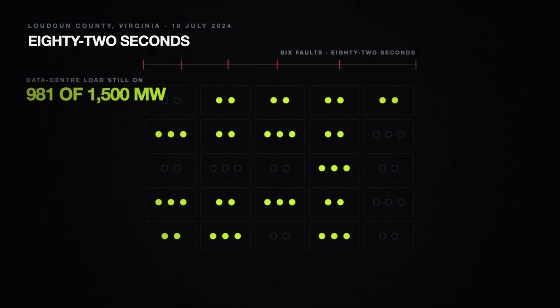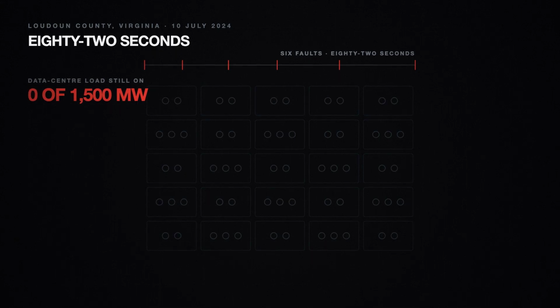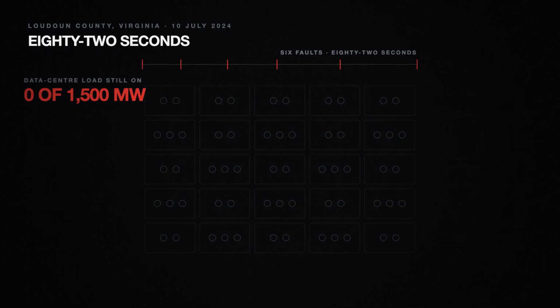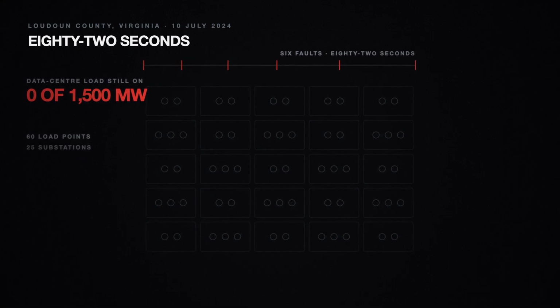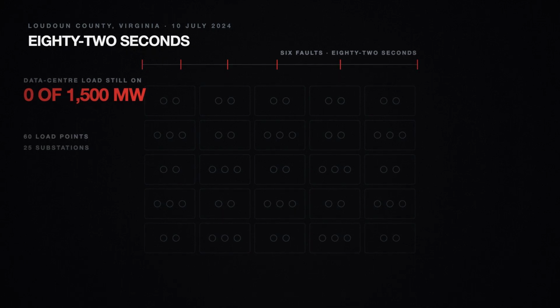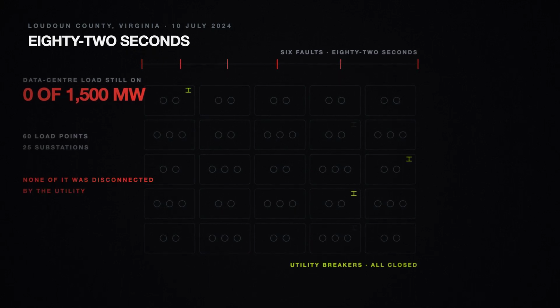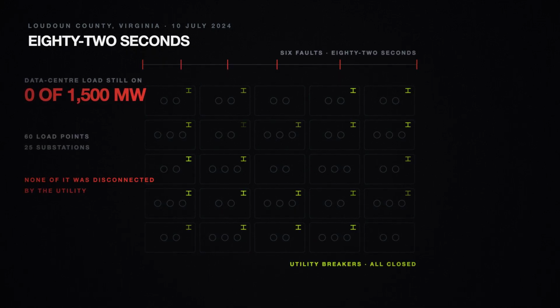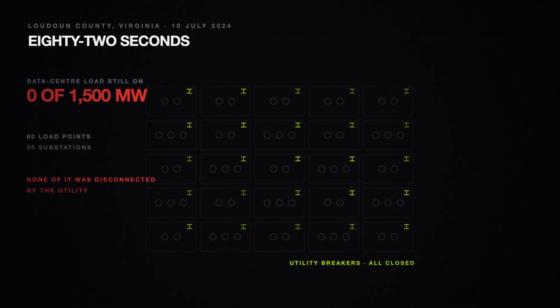And in those 82 seconds, about 1,500 megawatts of electrical demand vanished from the grid. Not a power station. Demand. 60 separate points of consumption across 25 substations in Loudoun County, Virginia, the densest concentration of data centers on Earth. Not one of them was disconnected by the utility. Every one of them left on its own.